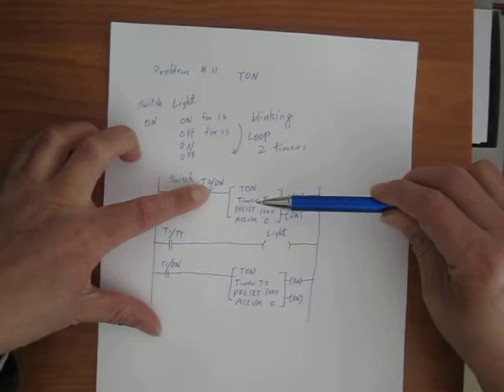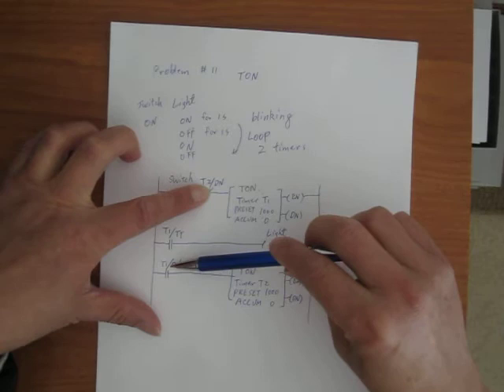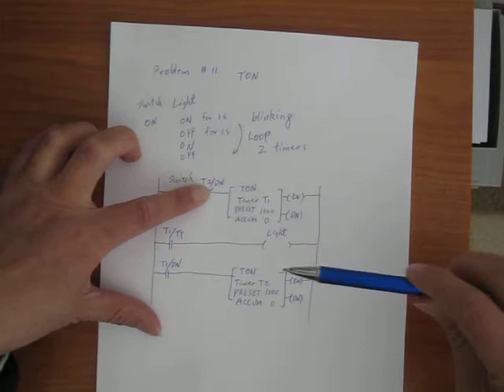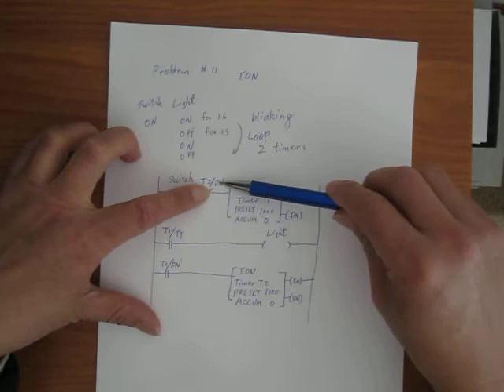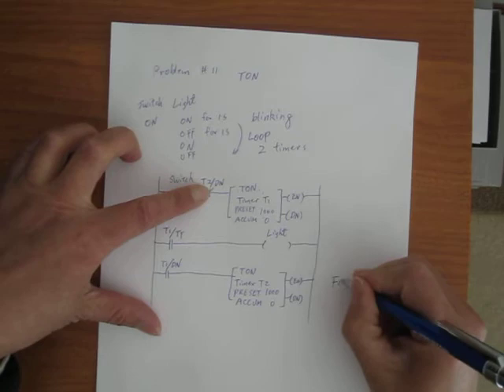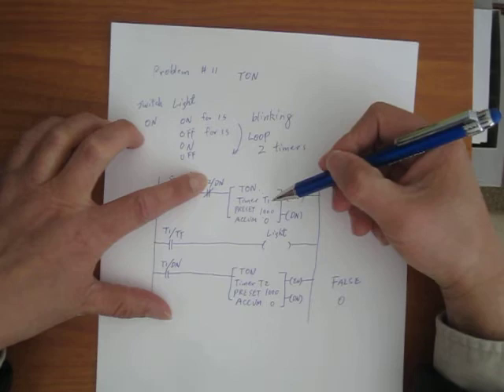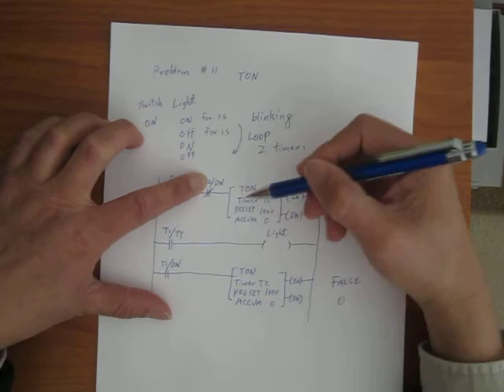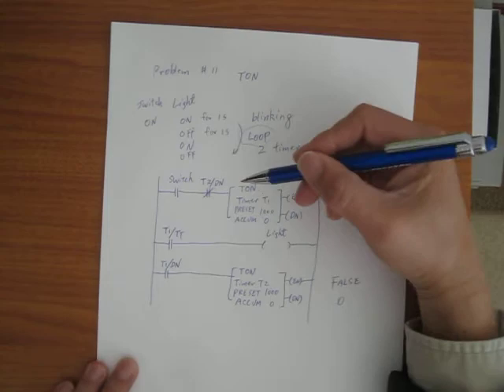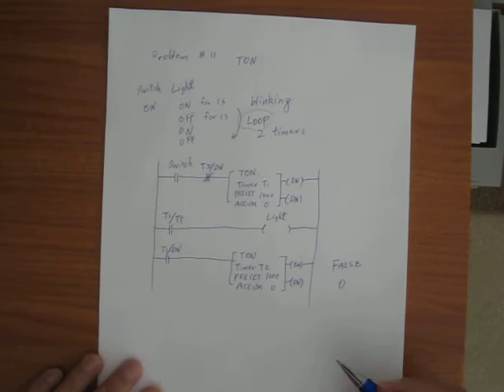After one second, T2 DN becomes true. NOT of true is going to be false, which turns T1 off. Once T1 turns off — almost in a millisecond — T1 DN becomes false. That turns T2 off. Once T2 turns off, T2 DN becomes false, becomes 0. So NOT of 0 becomes 1 again, and then it turns T1 on again. That's how we loop it.